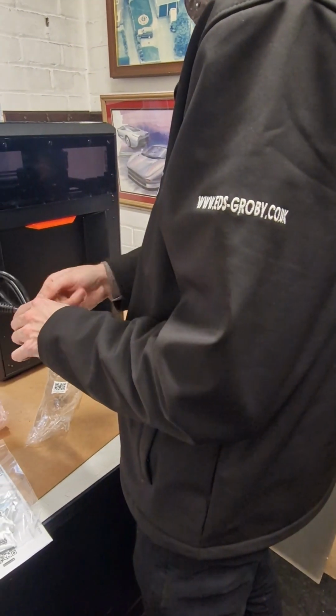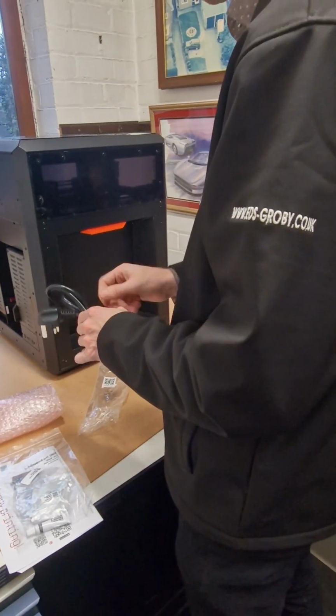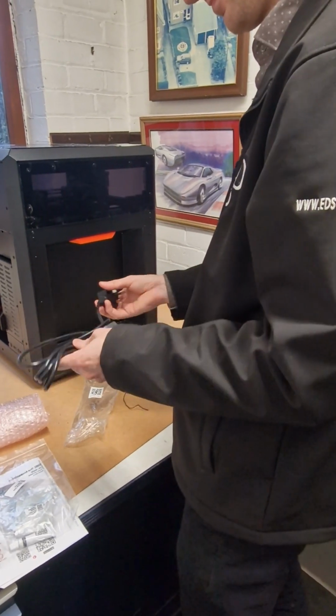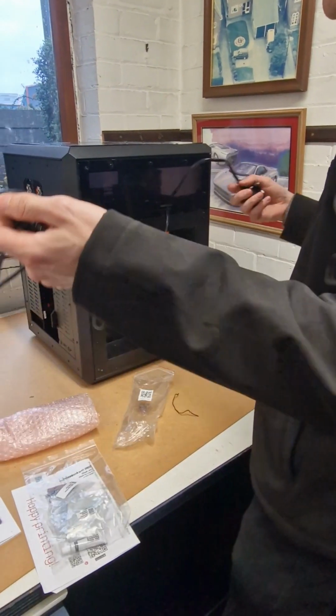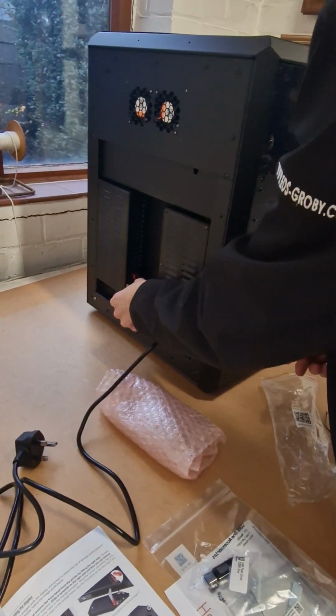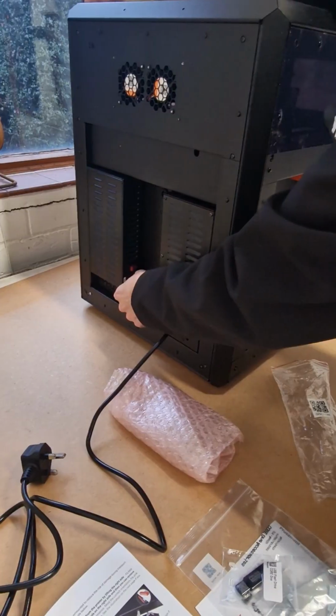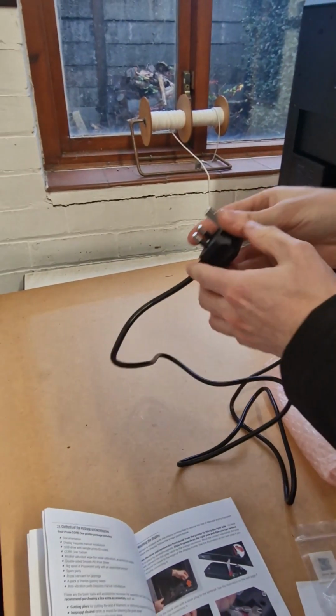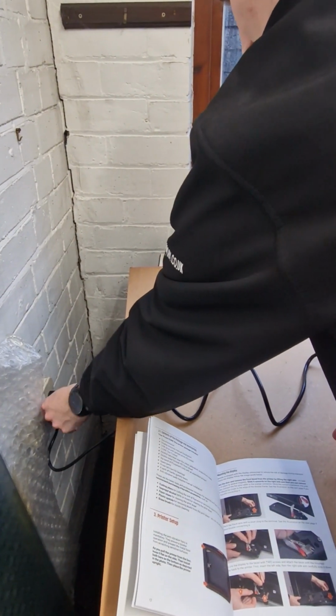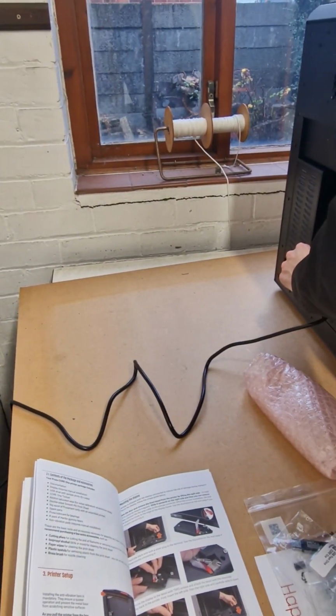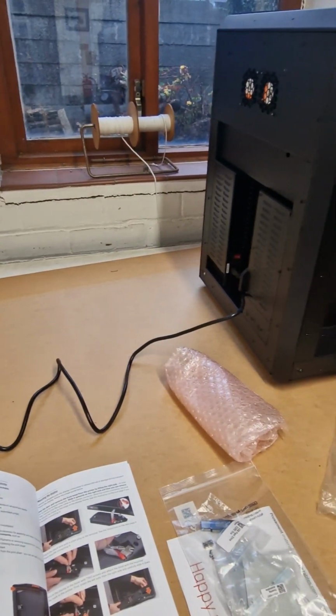This is located on the rear side of the printer. Before you plug or unplug the cable, turn the printer off using the physical switch on the power supply unit next to the power supply port. Always remember, pull the connector. Do not pull the cables itself. Incorrect handling can lead to damage to the connector or cable. The next section we have sped up, but the calibration took around 5 minutes.